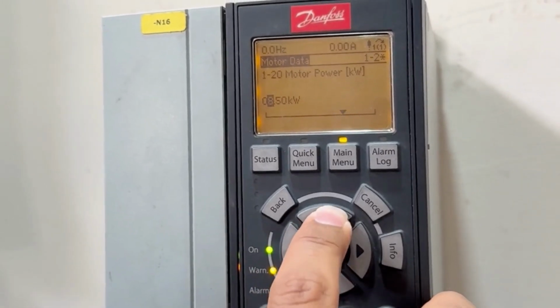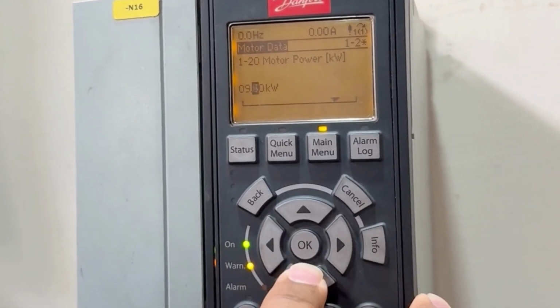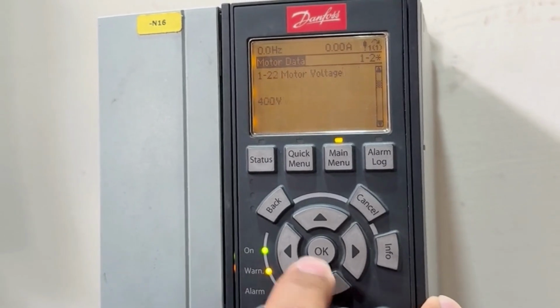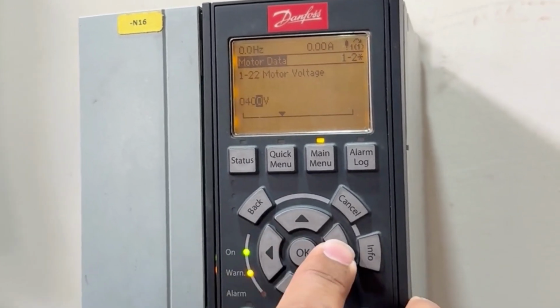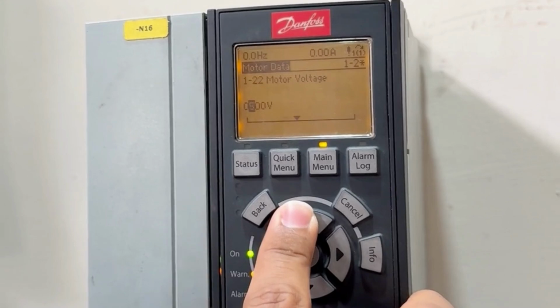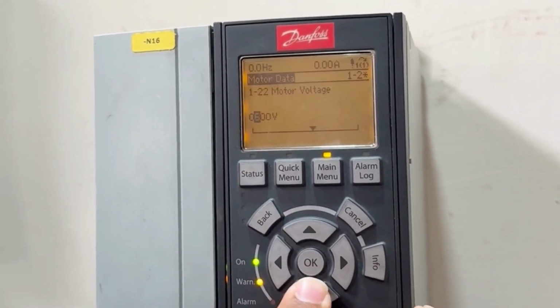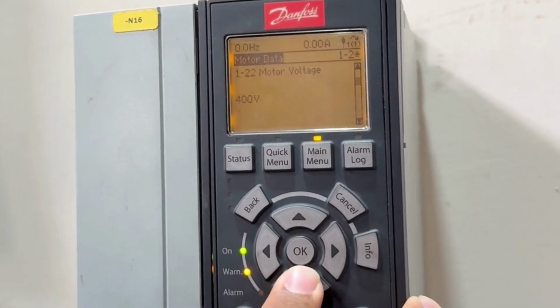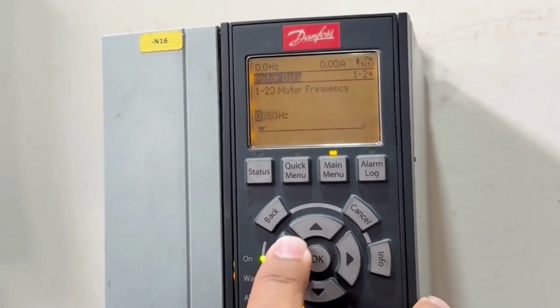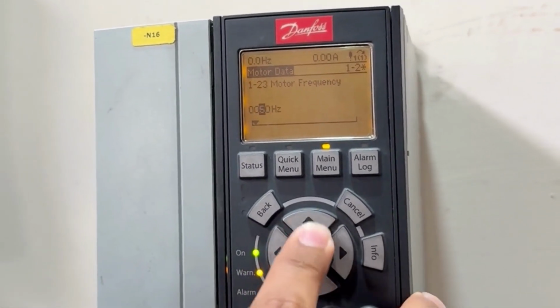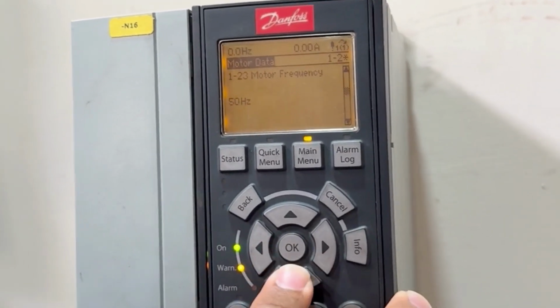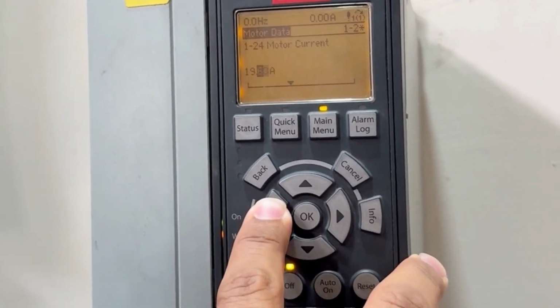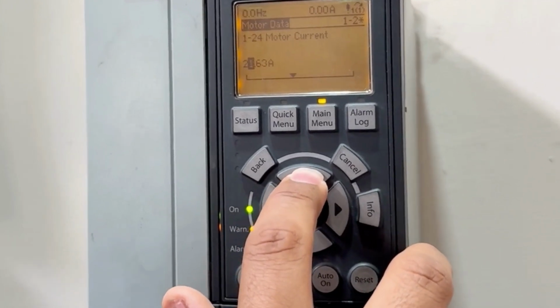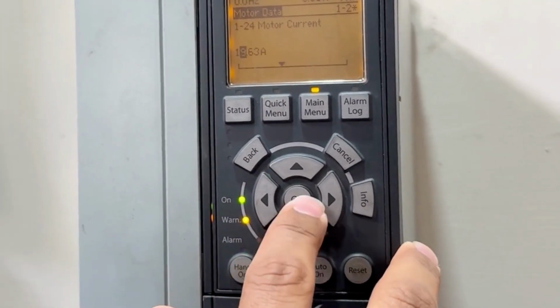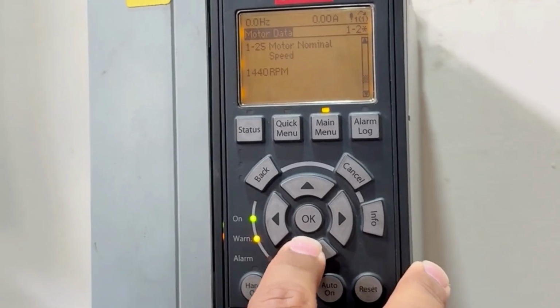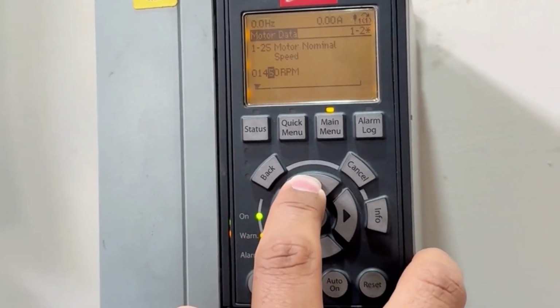Here, we set the motor power, then the motor rated voltages, followed by the rated frequency, which is 50 Hz. Next, we enter the motor rated current and finally the motor rated speed in RPM. After entering all the parameters, the VFD is set and ready to control the motor for the speed probe testing setup.